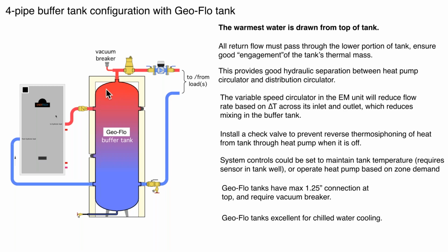I'm showing the indoor unit of the air-to-water heat pump piped up to the tank. Here's the check valve, so we don't get that reverse flow back during the time when the heat pump is off. But I'm taking the outlet to the load off the very top of the tank. You know, it's conceivable you could take it off here, but the reason that I'd like to see it up at the top is you're getting the very hottest water in the tank. And there is some slight temperature difference between this level in the tank and the very top. Remember, the hottest water in the tank is going to be the lowest density. It's going to be up at the very top.